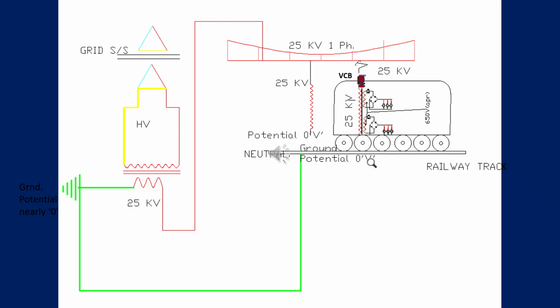We are taking power supply from the grid supply substation in three-phase form. Then in the traction substation, we are using two phases, stepping it down to 25 kV. One end is given to the OHE and another end is grounded solidly to earth and connected with the railway track. So it is working as a single phase system. The OHE is the phase and the ground is the neutral. It is just like our home appliances' single phase system, phase and neutral.